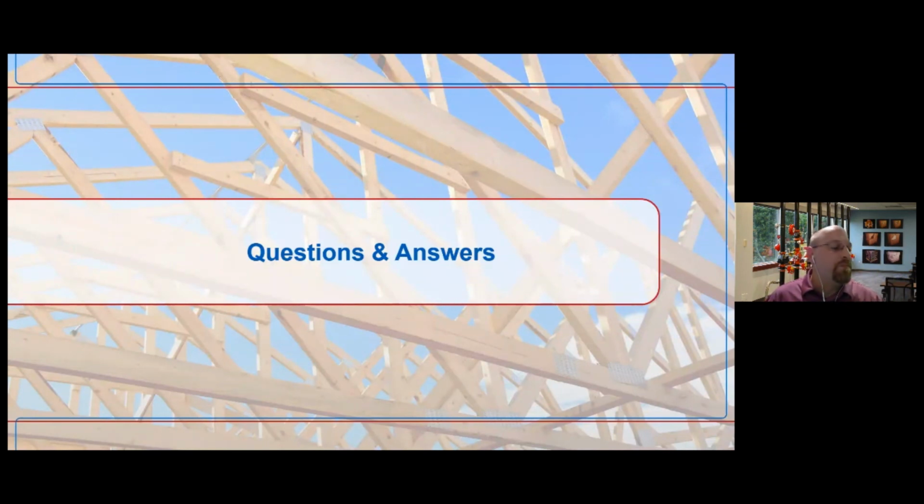Thanks, Brandon. Obviously, you did a wonderful job again. We have one question that has come in, and that question is, the GP56, can you use these back to back on a dual slope up to 30 feet wide as long as they are 6 feet apart without a draft curtain? That would be in line with our dormer installation for that product, so I would say yes. And I would agree with you.